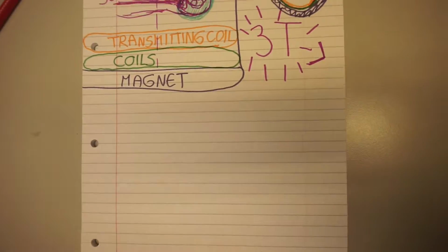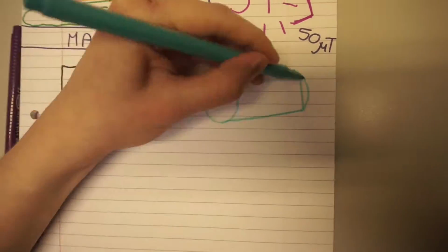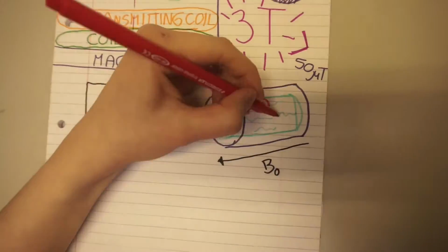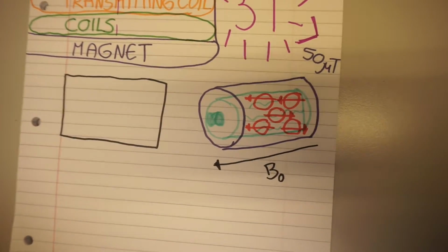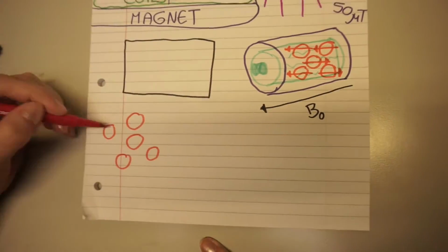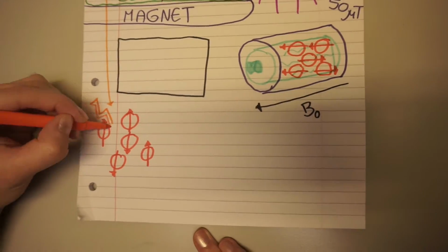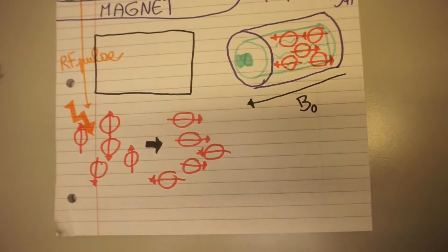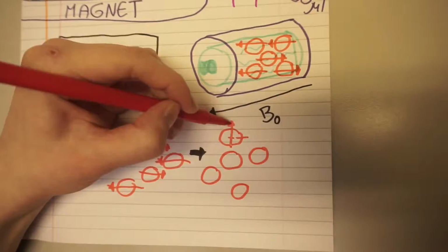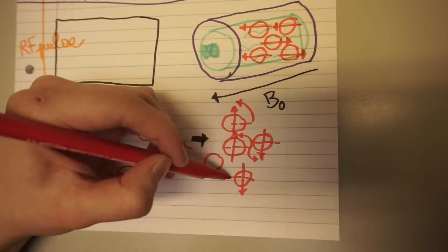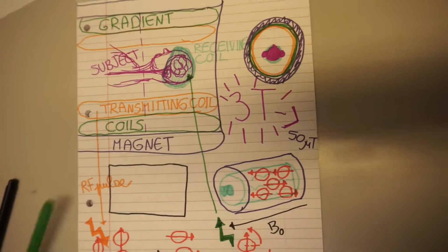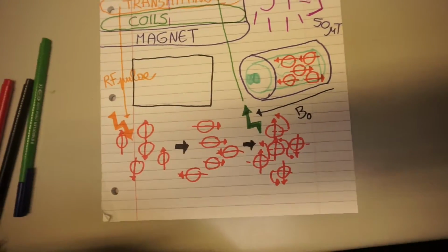So, you might be wondering, if we have signals coming from all over the object, how do we know where each signal is coming from? To locate the signal, we add additional magnetic field gradients, using the gradient coils to change either the phase or frequency of the proton's precession in the wanted direction. This way, each part of the image will have a radio frequency pulse coming with a frequency and a phase intrinsic to its location of origin. We record the frequency, phase, and intensity of the RF signal for each location and mathematically transform this data set to produce an image.